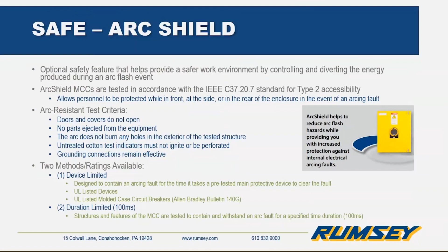The test ensures that all the doors and parts remain attached to the enclosure and that there's no ignition during an arc flash incident. There are actually two options or ratings available in ArcShield. You can get either device limited or duration limited. The device limited rating contains an arcing fault long enough for the main protective device to clear the fault. And duration limited contains and withstands an arc fault for a specified amount of time, which in this case is 100 milliseconds. And throughout the next couple of slides, we'll go further into each of these and compare them.